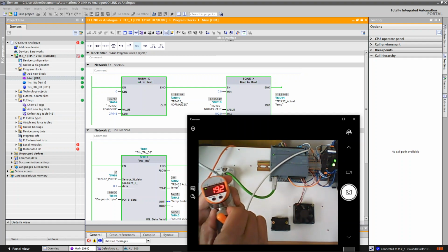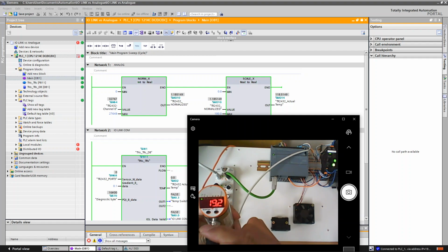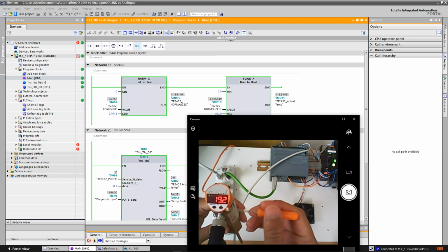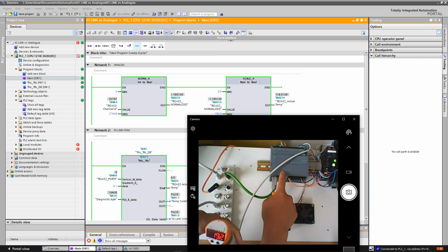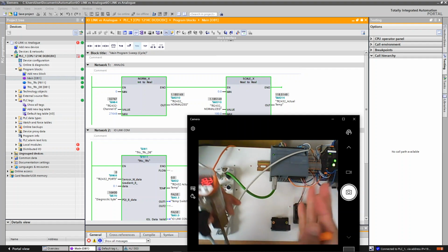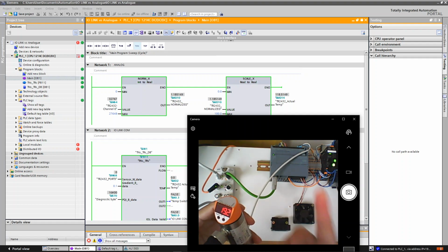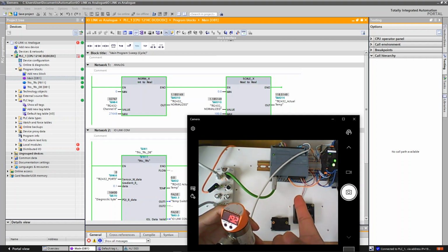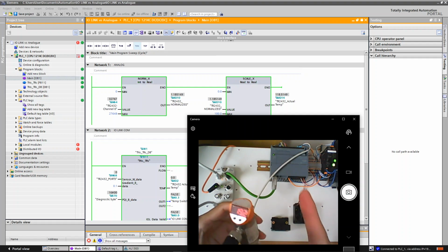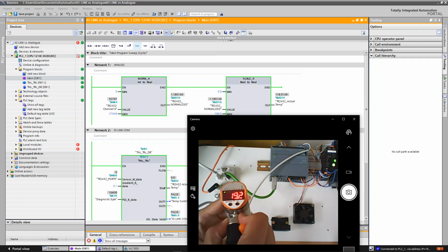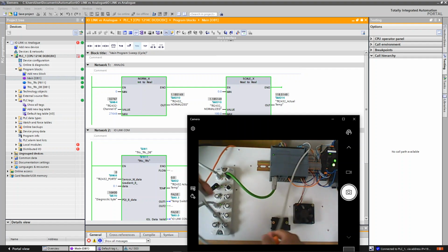You know why? Because the factory default analog output of this sensor is current, and our PLC only accepts voltage. So that is one of the problems that you might encounter in the field. You might accidentally feed a current into an analog input card, which is voltage. So that's why you have an error. That is one of the problems that you might encounter with a traditional system.